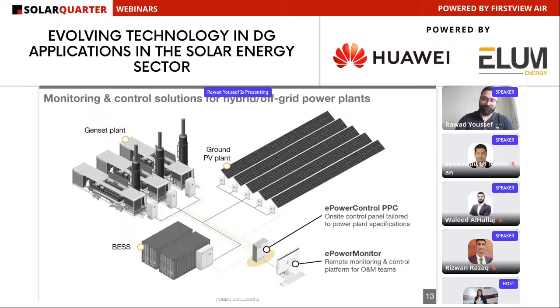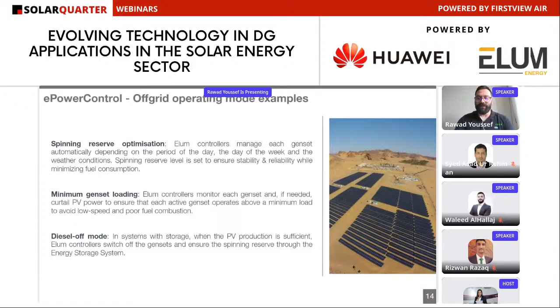Going through some examples of what we provide with these controllers: spinning reserve optimization, either from the BSS part or the genset part; minimum genset loading; and in some cases diesel-off mode. If the equipment available on site allows changing the grid-forming units - for example, the BSS can be the grid-forming unit of the whole system - then we can turn off the gensets completely in order to reduce fuel consumption as much as possible.